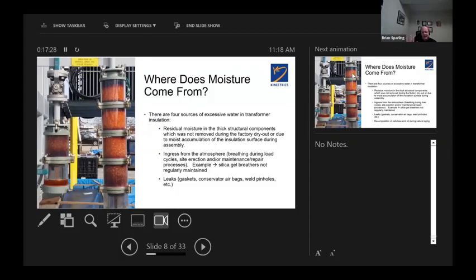When you have a leak through a gasket or whatever, from the inside to the outside, oil may be seeping out. It doesn't have to be dripping out, just seeps. You've created a two-way highway: oil is coming out, but at the same moment, air from the ambient and moisture from the ambient is going in. It's a molecular highway now. So that is one big reason why moisture gets inside the tank of a transformer: through leaks. So when you see leaks, big or small, seeps, whatever, please take time to fix it, because you're only contributing to a reduction in life of the transformer because of accumulated moisture that stays inside the tank.